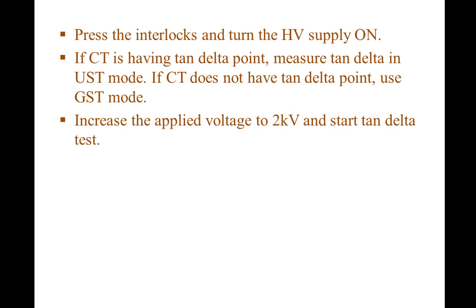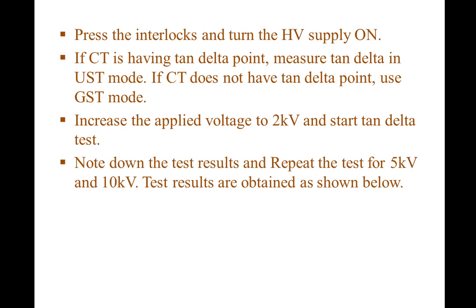After doing all the connections, press the interlocks of the kit and turn the high voltage supply on. Increase the applied voltage to 2 kV and start the tan delta test. Note down the test results and repeat the test for 5 kV and 10 kV.